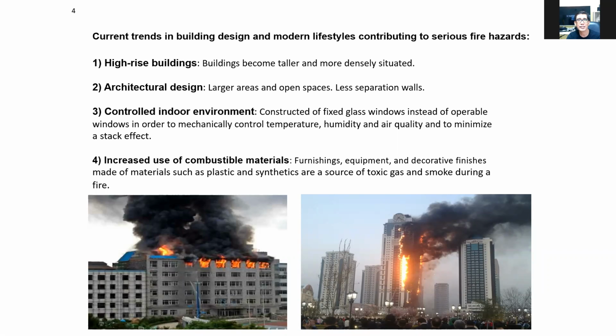So that is also one problem of high-rise buildings or for commercial buildings. They tend to minimize the openings or the operable windows, like in shopping malls that were built during the 1970s or 1980s, where the perimeter of the buildings is enclosed with firewalls or windows, so there is no means to open the windows in case of smoke inside the building. Another one is the increased use of combustible materials like furnishing, equipments, and decorative finishes made of materials such as plastic and synthetics, which are a source of toxic gas and smoke during a fire. So that is also one problem.